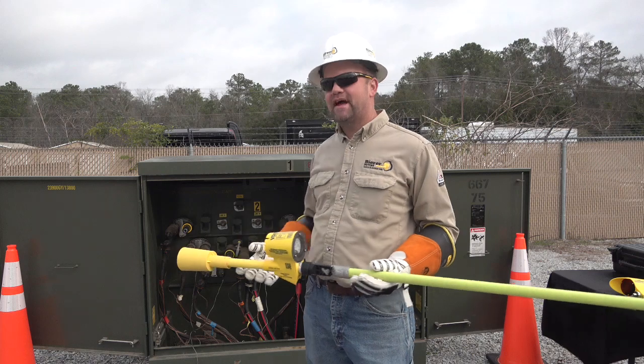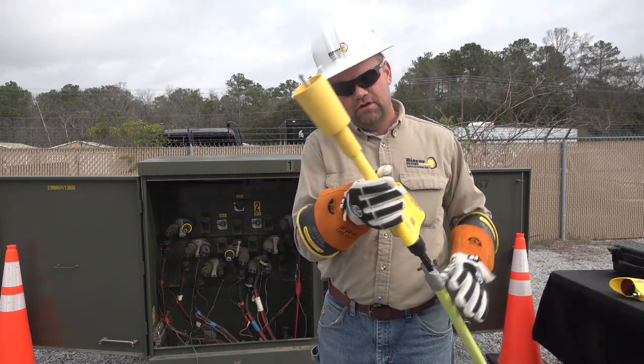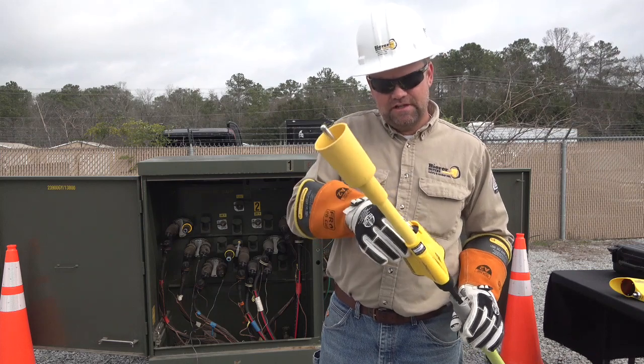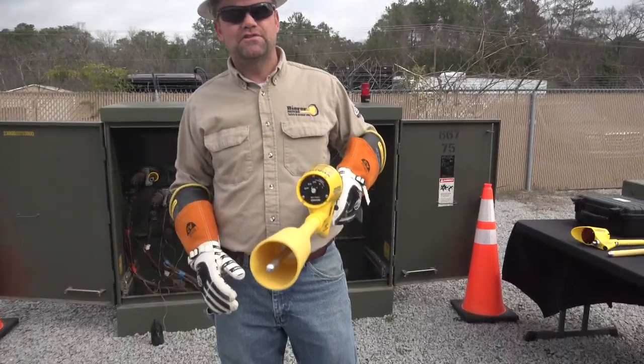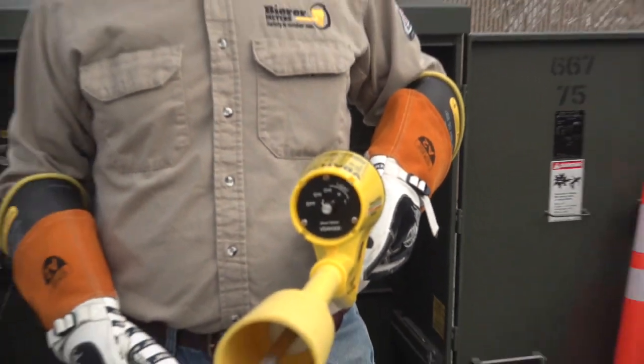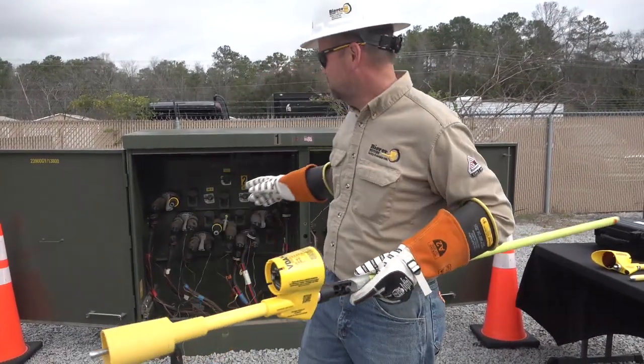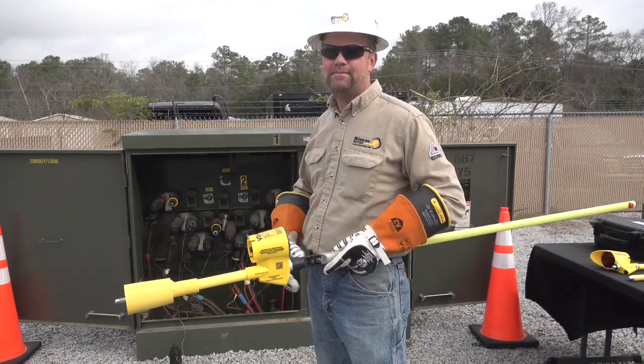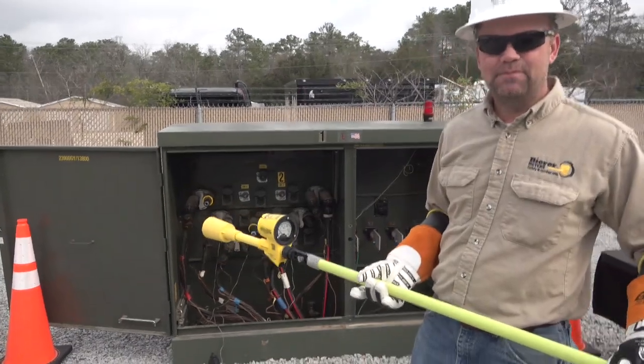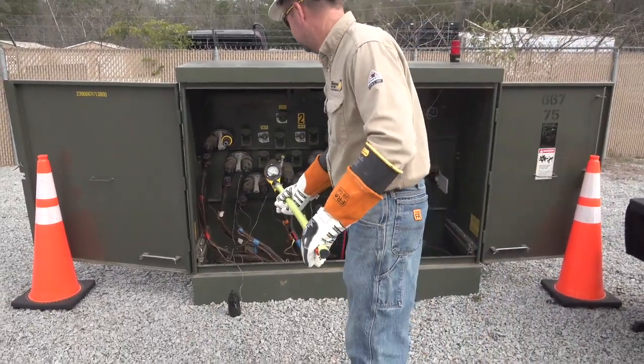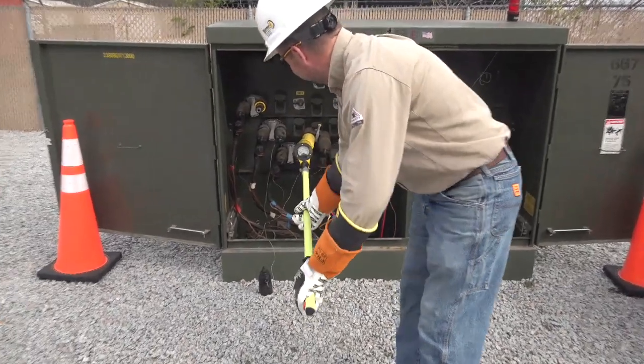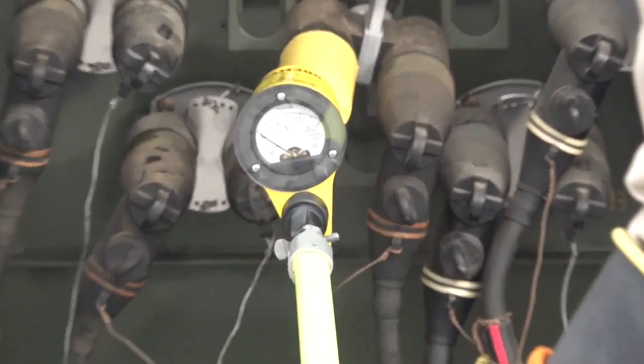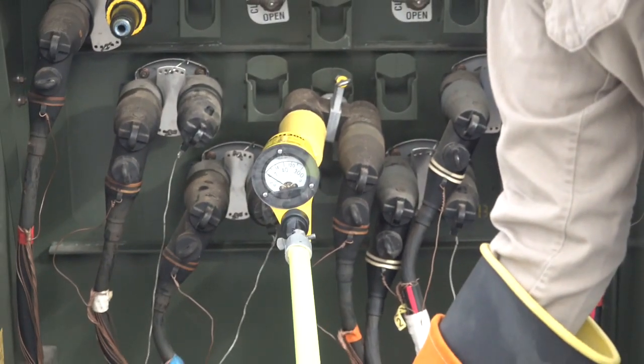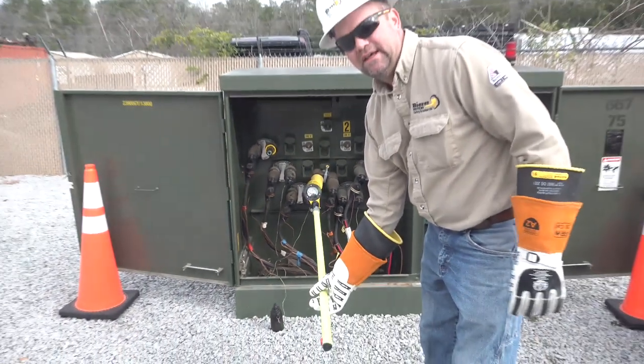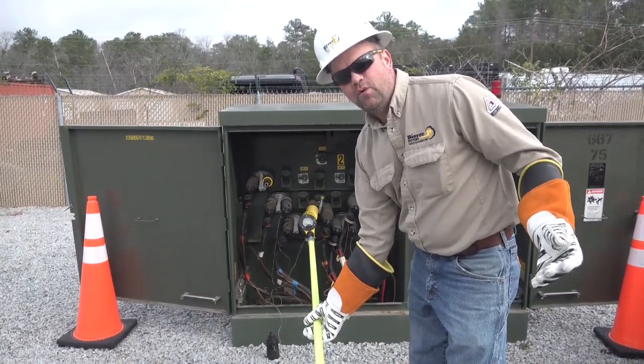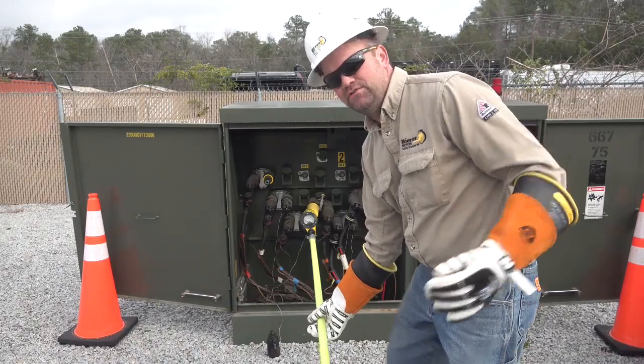So I'll go ahead and check for my de-energized first, and I want to turn the device to the first on switch position. So I have it in the first on switch position on my switch, and I go ahead and put it in the bushing where I have a cable stood off on a feed through in our cabinet behind me, and check for de-energized. Make sure that cable is de-energized. So I have the bushing adapter inserted all the way in, and notice the needle stays on 0, displaying 0 potential. Remember, I've tested this device before I used it. Now I want to test it after I use it.